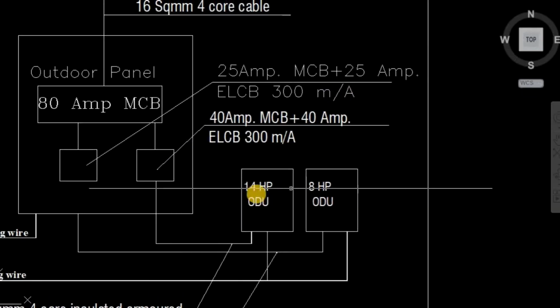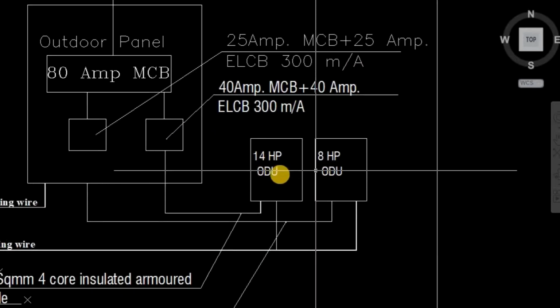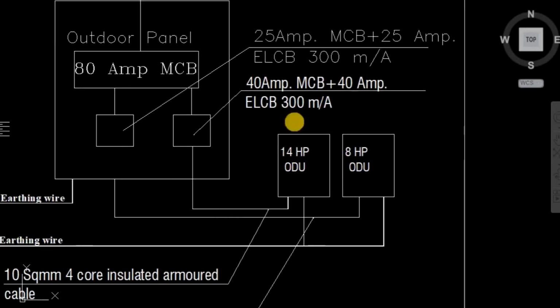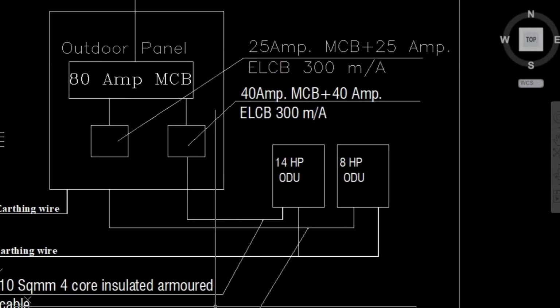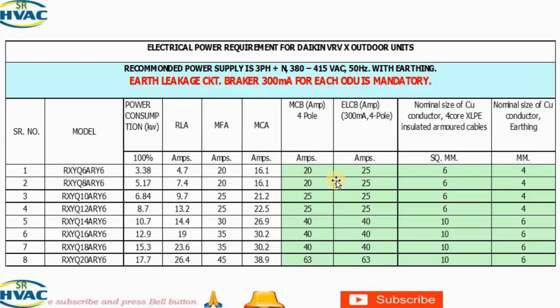This you can see, this is a 14 HP and 8 HP outdoor unit. This is 25 and 40 MCB. So we can check for 8 HP. You can see it is 20. MCB is 20, and this is 6 square mm, and the 14 you can see this is our 40. MCB will be 40. So we can check here.